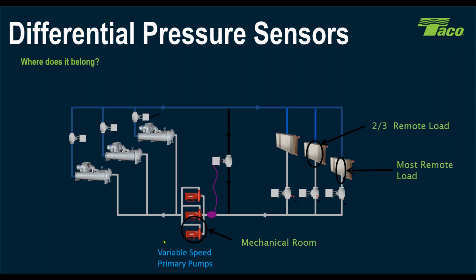It's the cheapest place, or I shouldn't say cheapest, but there's not as much wiring though, Tony. That's why I put it there. Yeah, and that's what I usually hear, Brett, I hear that all the time, is they put it there because they thought that's a good place to put it. Well, it's not, because you end up over pumping the system. You end up spending a lot more pump energy trying to meet that most remote load. You get no savings from having it.